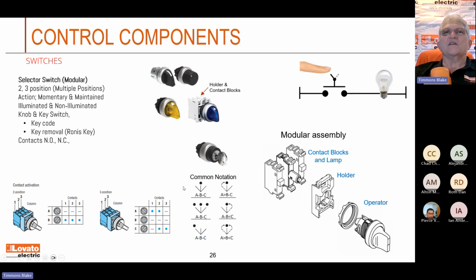Some common notation I like to show everybody at the bottom here: that first one is a maintain, it just says ABC. And then look at the one to the right of that. That's a spring return from the A side, from the left side. And here you are in the 3-pole switch. You've got an ABC there, and they're all maintained. And these are key removal. Usually when you see a dot above it, that's where I can take the key out. So if it's one of those key switches, that's the location where I can take the key out.